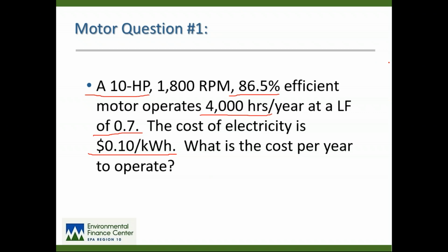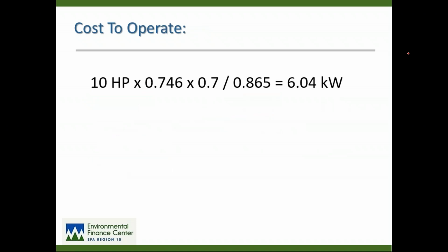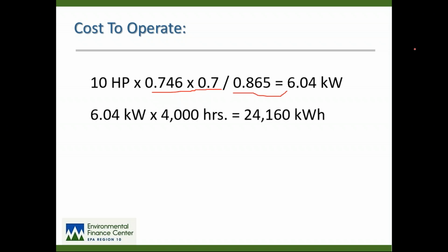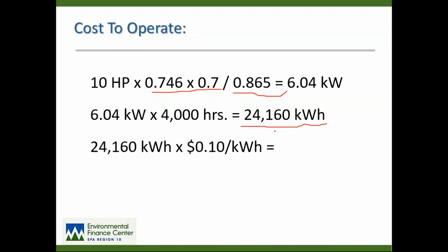So the question is, what's the cost per year to operate? That's the first thing we want to know, how much this is costing us every year to run this one motor. So we just run the numbers. Horsepower times loading divided by efficiency is just a little more than 6 kilowatts. 6 kilowatts times hours gives how many kilowatt hours per year. Kilowatt hours per year times cost of energy is $2,416. Pretty easy, right? Just basic math.